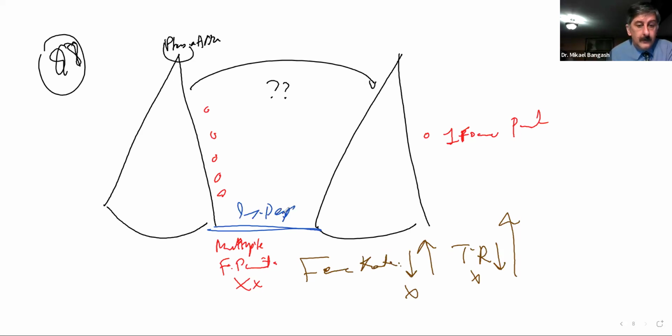The imaging depth is the same. Please, guys, do not confuse imaging depth with focal depth. The only thing you can say about focal depth being related to imaging depth is that the focal depth has to be within the range of your imaging depth. You can't have an image 5 centimeters deep and try to focus at a depth of 7 or 10 centimeters.